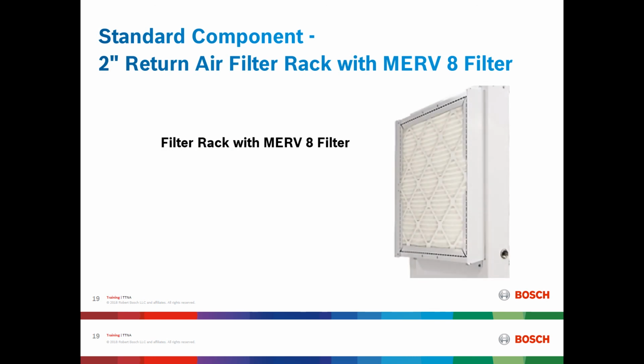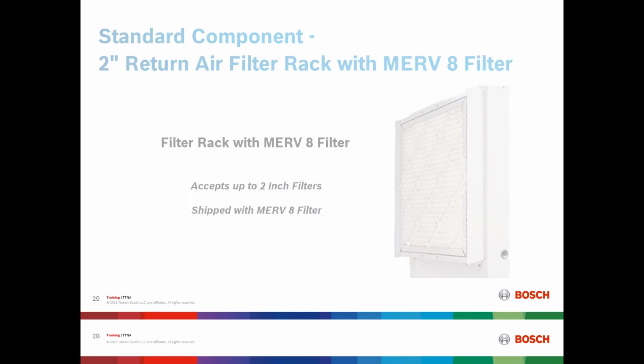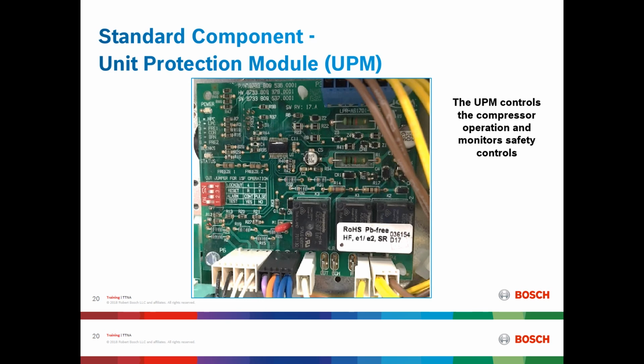The unit will come with a 2-inch air filter rack with a MERV8 filter. It accepts up to any 2-inch filter, and the filter will be shipped with the machine. The control board for the REV-V model is a unit protection module, or we refer to it as a UPM. This is a high-tech control board and controls the compressor operation and monitors the safety controls.